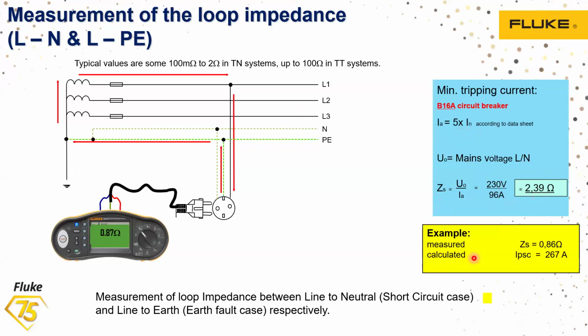And under this condition, when you use a meter and check it, if you get a resistance lower than 2.3 ohms, it indicates that the path is very low, and it can easily allow close to 267 amperes. So it means that as per the circuit breaker, if it is a 16 ampere circuit breaker, the expected current can go up to 96 ampere. But here, the short circuit current can be as much as 267 ampere, which is a little bit higher than expected.